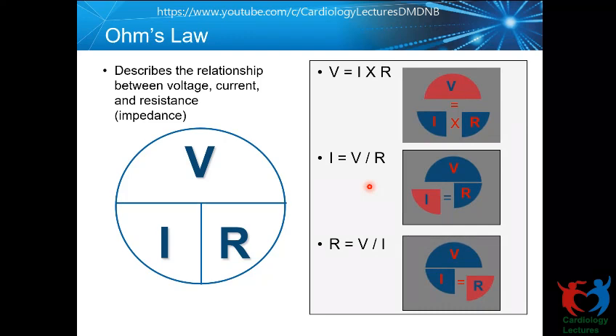So going by this, current is the voltage divided by the resistance. That means if the resistance is higher, then the current outgo becomes lower. When within normal limits, if the current outgo is lower, the energy outgo from the battery is going to be lesser. We will see some more details of that. And then the battery is expected to last a little longer for this patient. But if this resistance becomes significantly higher, then a very low amount of current flows through, which may not be adequate to capture. And that is what usually happens when the lead fractures. Then the impedance is going to be higher.